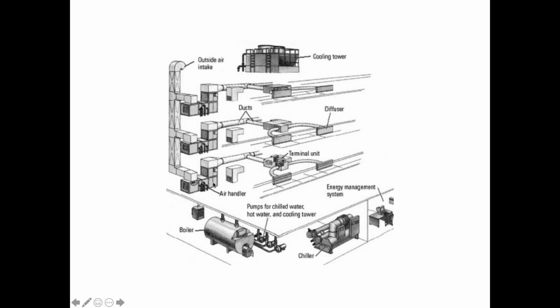So they have coils in there, right? Well, the problem with Freon is that when you're sending it through these tubes, they have to be insulated, they can't be too long, the Freon can condense in them, and they can do weird things, and it doesn't turn out very efficient. So it's a real problem to have Freon lines running throughout a building. Very expensive, that's under a lot of pressure and so on and so forth. If they leak, it costs a fortune.